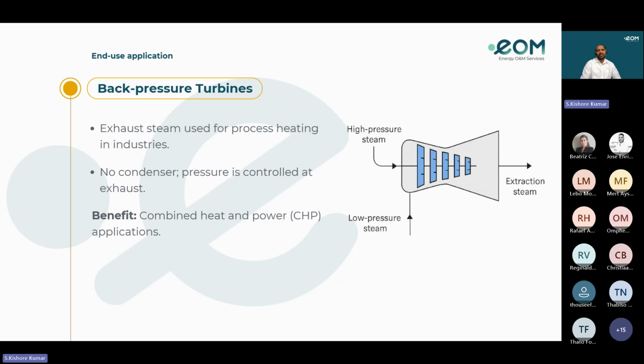Coming to the back pressure turbines. A back pressure turbine is a type of turbine used primarily for combined heat and power (CHP) or industrial processes, where steam is expanded only partially and the exhaust steam is intentionally kept at high pressure for use in industrial processes. Exhaust steam is used for process heating in industries, there is no condenser, and pressure is controlled at exhaust. The benefits are combined heat and power applications, and the examples are paper mills, sugar factories, textile mills, refineries and petrochemicals.